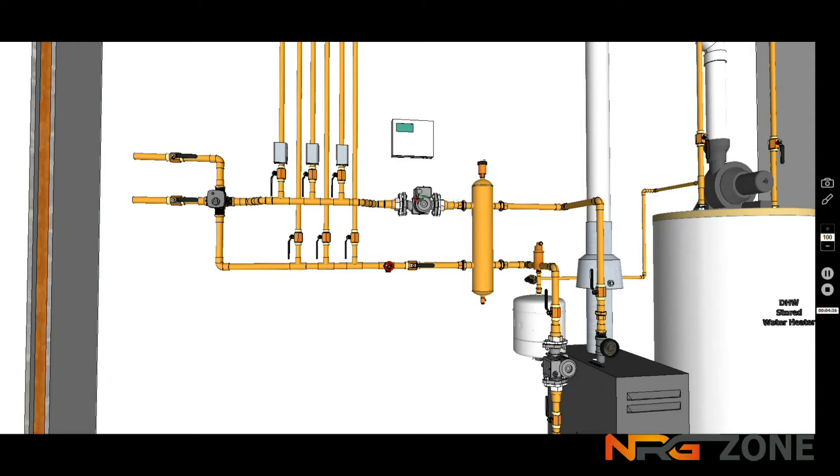On the secondary side, you have a pump that pushes water out. If you have a low temperature system here, you could have the pump pushing through two ports of a four port valve and back to the low loss header around in this circuit. And of course, it's passing the three valves shown in this example, where one might be for a living area, one might be for a formal area or a conservatory, and the last would be for something like a bedroom circuit. The pump is just continually pushing water around the low loss header when any of these zones is calling.